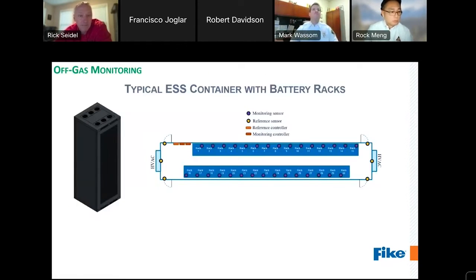Next, please. In a typical energy storage system container application, this is what the off-gas detection system layout may look like. We'd have one monitoring sensor in each rack, again, strategically located downstream in the circulating airflow. We'd also have reference sensors provided to establish a continuously changing baseline of calibration within the system and all detectors so that the monitoring sensors can remain as sensitive as possible, but adjust on the fly, if you will, based on external contamination that may be present. For example, an idling truck parked outside whose exhaust is being drawn into the enclosure. The reference sensor would read that baseline, adjust the monitoring sensors appropriately to not unnecessarily set off every sensor in the room just because of that external influence.